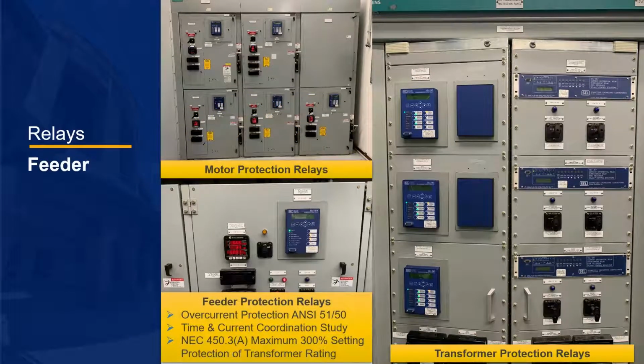Feeder protection relays are the most straightforward relays replaced in this project. They typically only include overcurrent protection, which are ANSI device codes 51, 50, and 50G. The time overcurrent protection, or 51, is set based on the manufacturer recommendations, IEEE 242 standard, NEC 450.3, and ETAP coordination results. In addition to the overcurrent protection, the main system feeder relays, configured in a main-tie-main scheme, support under and overvoltage protection to aid in the automatic transfer scheme.